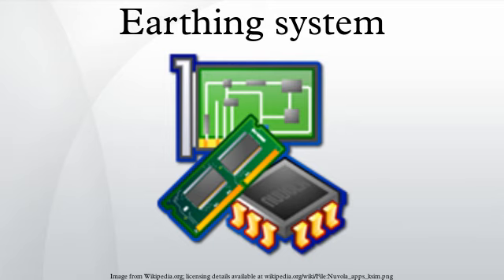In solid or directly earthed neutral, transformer's star point is directly connected to the ground. In this solution, a low impedance path is provided for the ground fault current to close and, as a result, their magnitudes are comparable with three-phase fault currents. Since the neutral remains at the potential close to the ground, voltages in unaffected phases remain at levels similar to the pre-fault ones. For that reason, this system is regularly used in high-voltage transmission networks, where insulation costs are high.